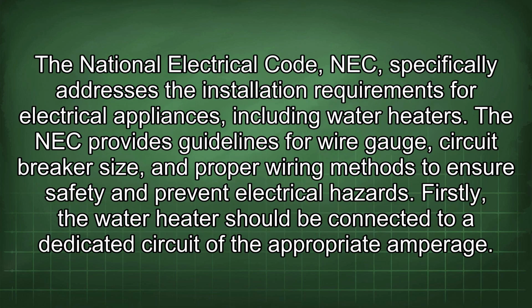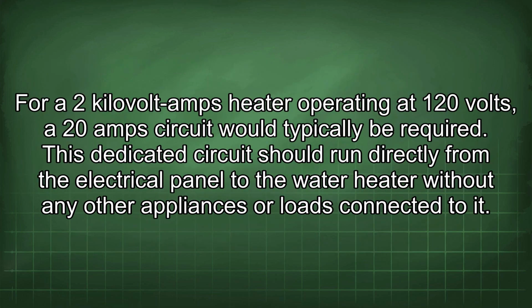The National Electrical Code, NEC, specifically addresses the installation requirements for electrical appliances, including water heaters. The NEC provides guidelines for wire gauge, circuit breaker size, and proper wiring methods to ensure safety and prevent electrical hazards. Firstly, the water heater should be connected to a dedicated circuit of the appropriate amperage. For a 2 kVA heater operating at 120 volts, a 20 amp circuit would typically be required. This dedicated circuit should run directly from the electrical panel to the water heater without any other appliances or loads connected to it.